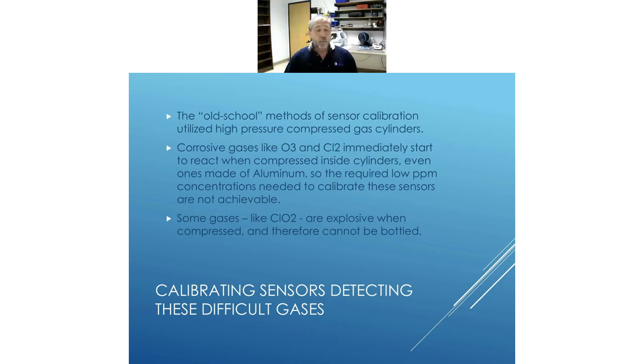So talking about how we used to calibrate these sensors, the old school method was a pressurized compressed gas cylinder used for a standard. It's still used today for most calibration gases, where you put a known amount, a low level of the gas in question, into a compressed gas cylinder, and then you use that cylinder with a regulator to apply it to a sensor, and then adjust that sensor to read the correct amount. So that's the basics of how we calibrate a sensor.